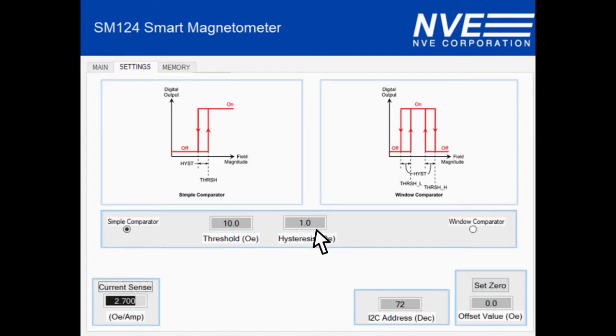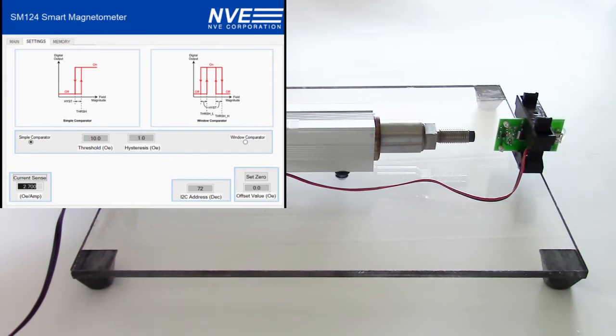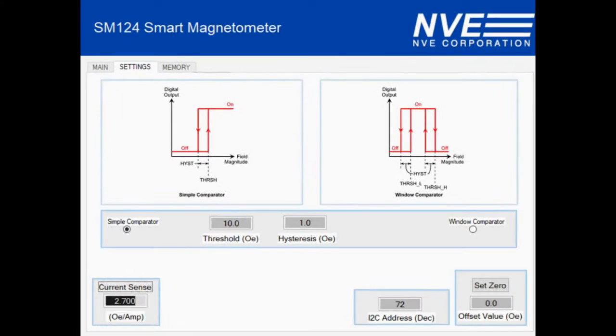The default turn-on, turn-off differential is small, but for this application, we set the threshold for 10 ersteds and the hysteresis for nine for a one ersted turn-off threshold.